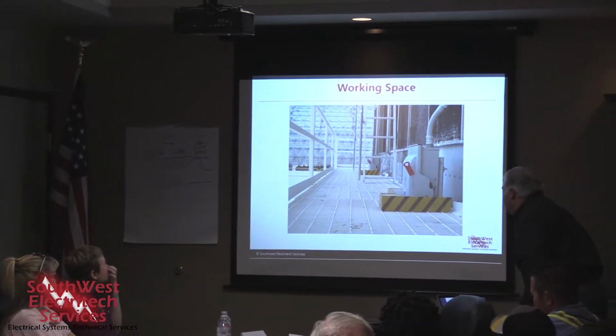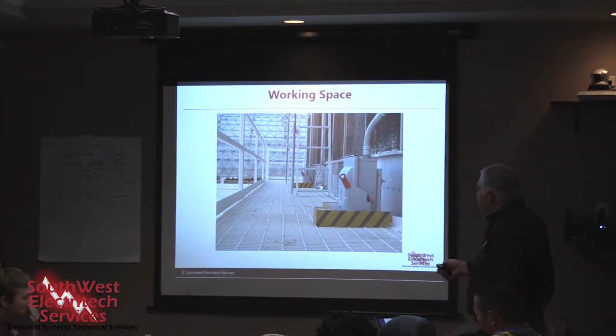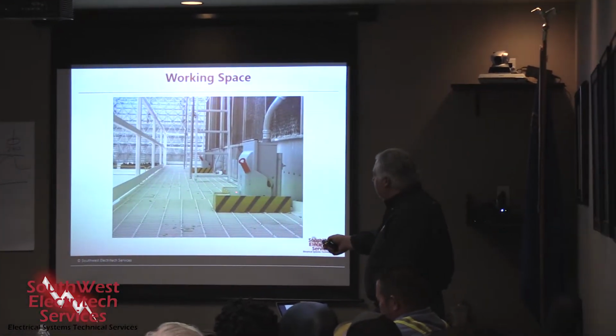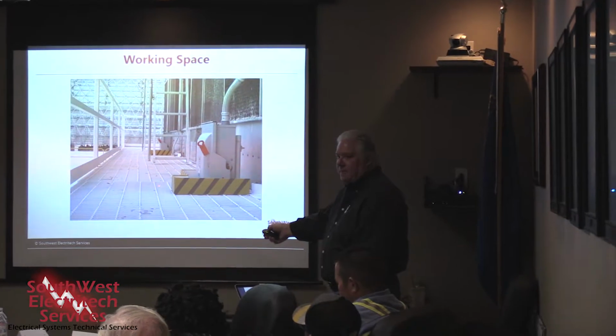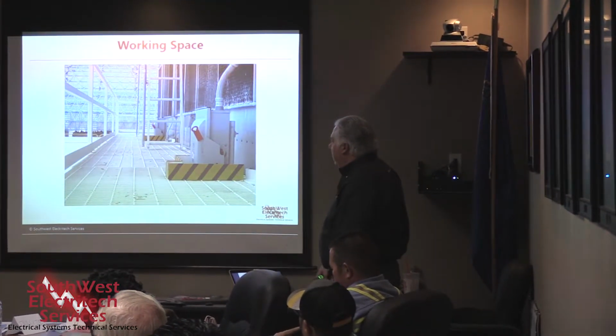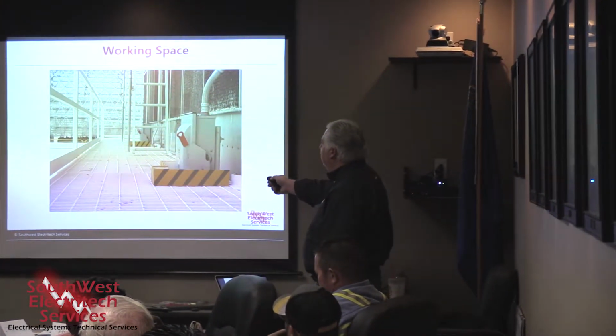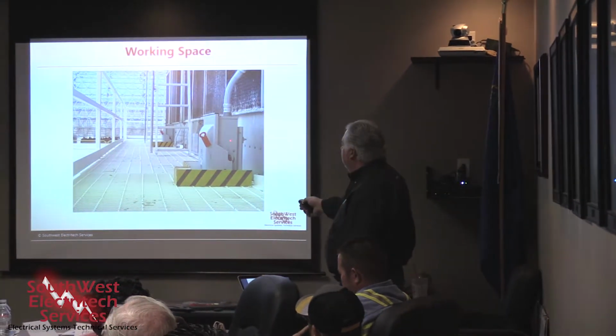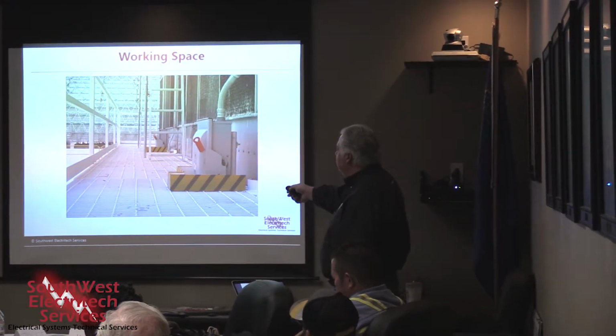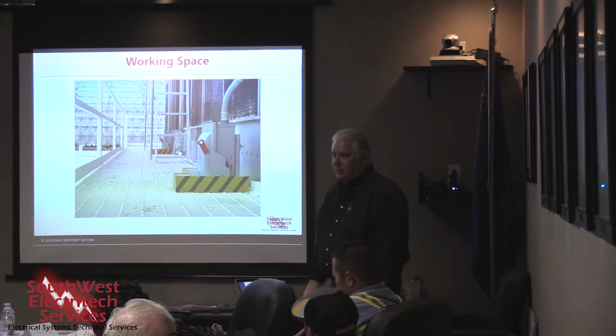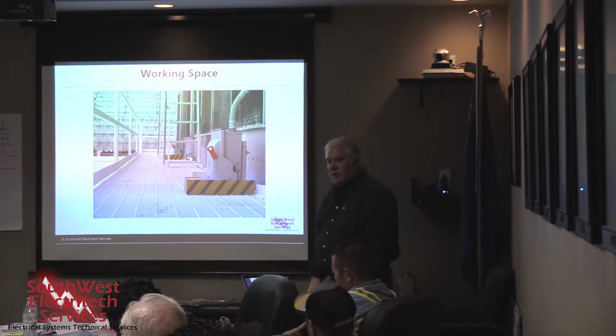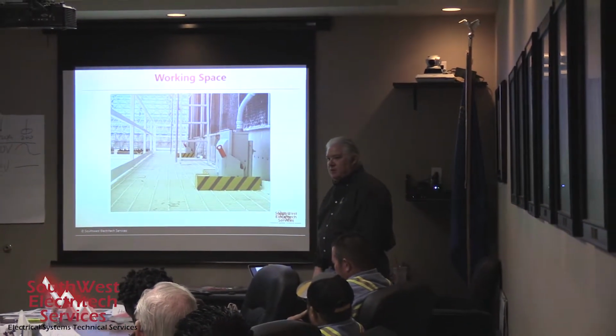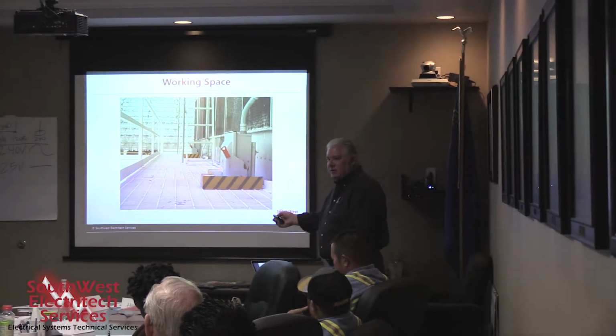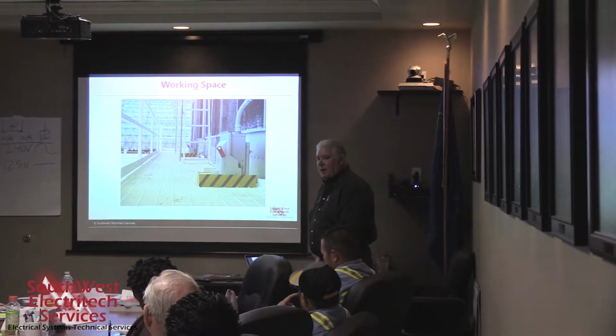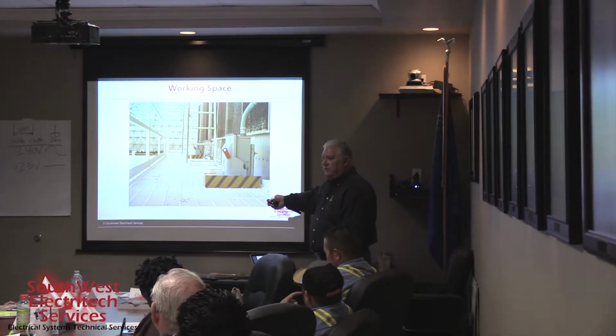Can I visually or electrically even bother testing this? I can't get the door open because of the kick plate in the way, right? Improper application, they should have been moved up. And I know it would have been a pain in the butt because you have a cooling tower, or they should have been moved down. But totally improper application here. So how would I verify that this was disconnected? I'd have to go to the breaker that fed this and verify it there.